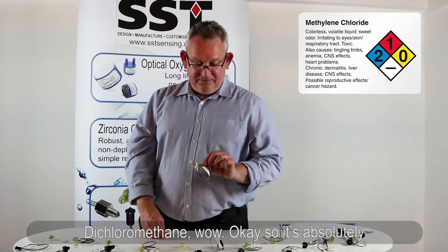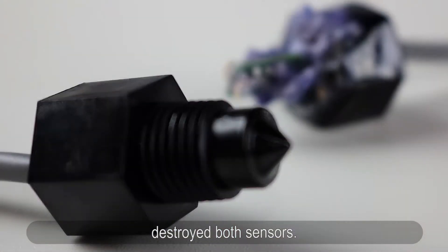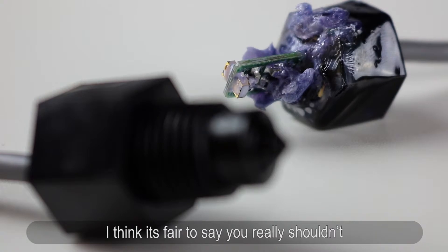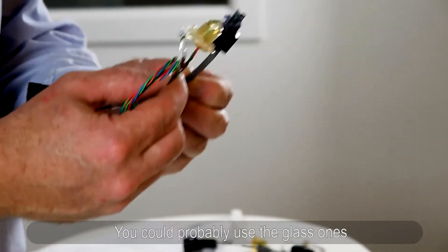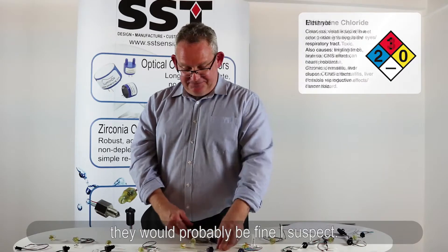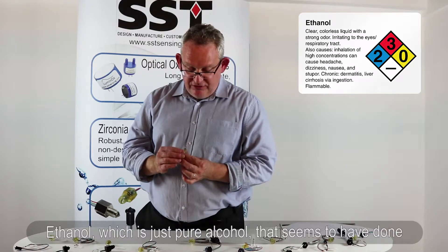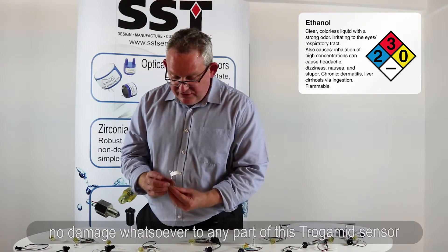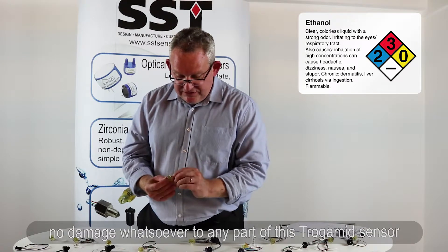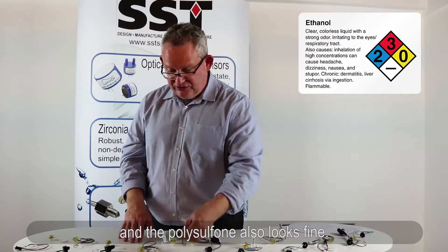Dichloromethane — wow. It's absolutely destroyed both sensors. It's fair to say you really shouldn't use our sensors in dichloromethane. You could probably use the glass ones — they'd probably be fine. Ethanol, which is just pure alcohol, seems to have done no damage whatsoever to any part of the Trogamid sensor, and the polysulfone also looks fine.